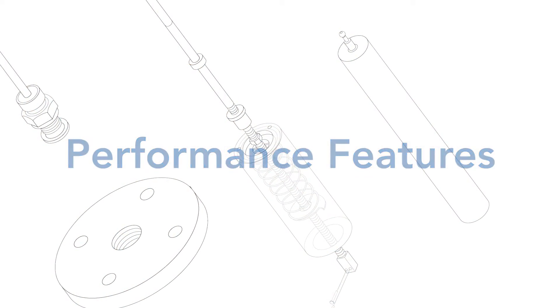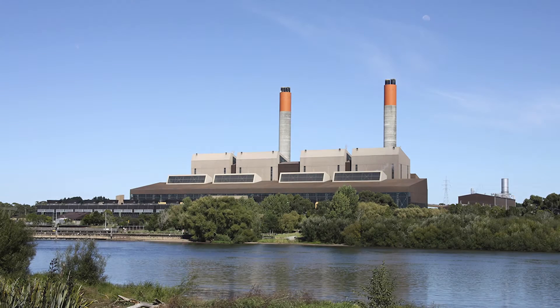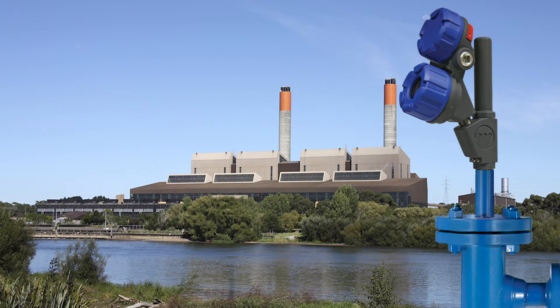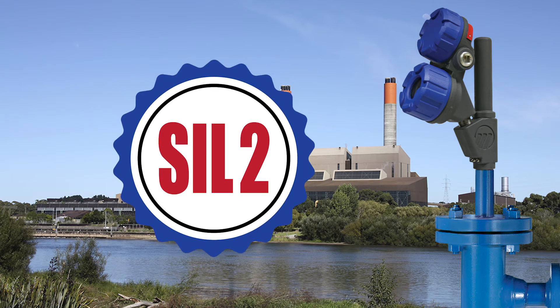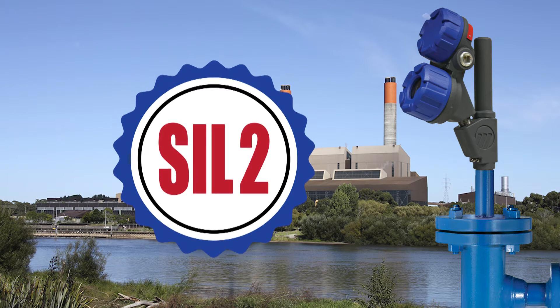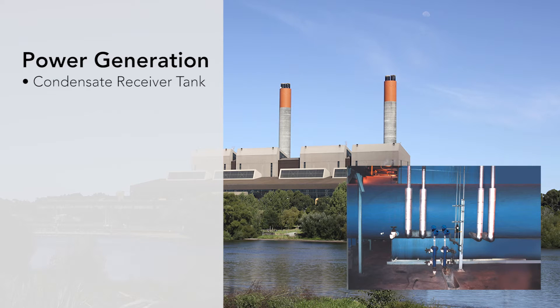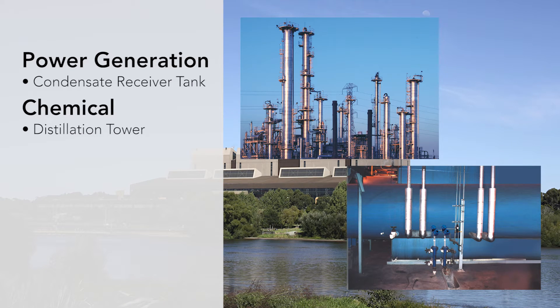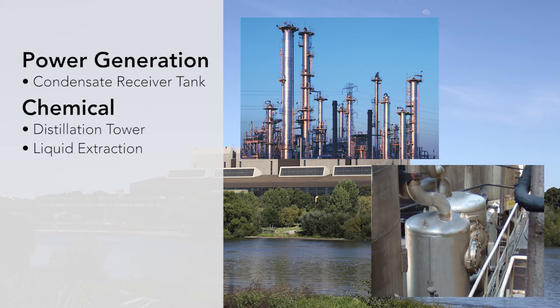Ease of use, superior performance and versatility make the E3 Modulevel a powerful level control solution for many process applications. It is SIL2 suitable and features a 92.3% safety failure fraction — higher than any displacer transmitter on the market. Displacer transmitters are ideally suited for clean or dirty liquids and slurries, from light hydrocarbons to heavy acids, and excel at liquid-liquid interface level measurement and density control.